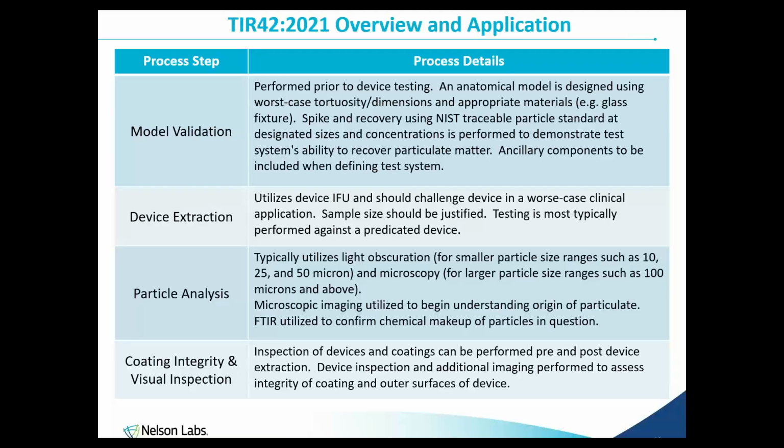Once your model is validated, you would go on to the device extraction. This is a process where we tailor the IFU to a particle test and essentially run through a worst case scenario. How many times can this device be inserted, reinserted before deploying a stent?